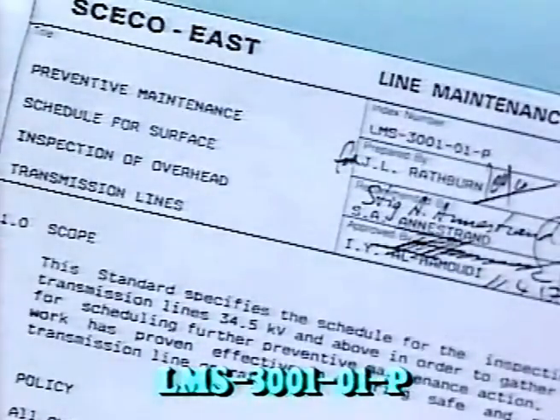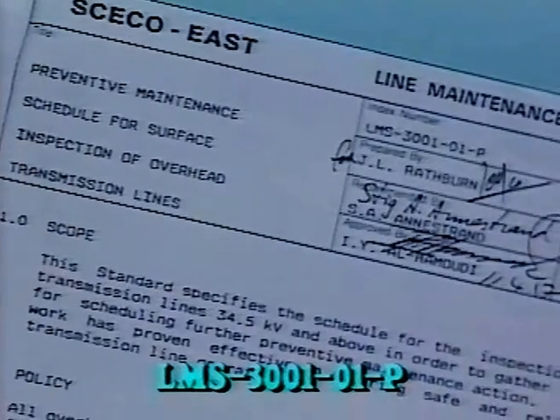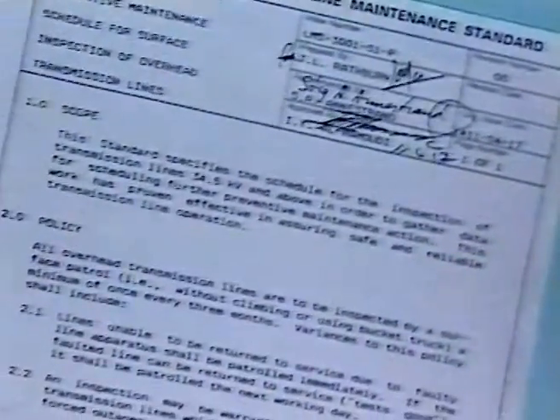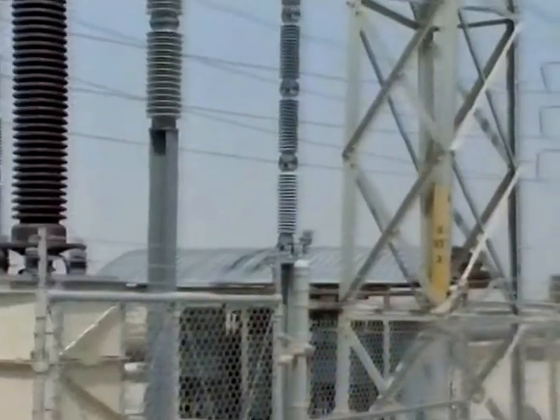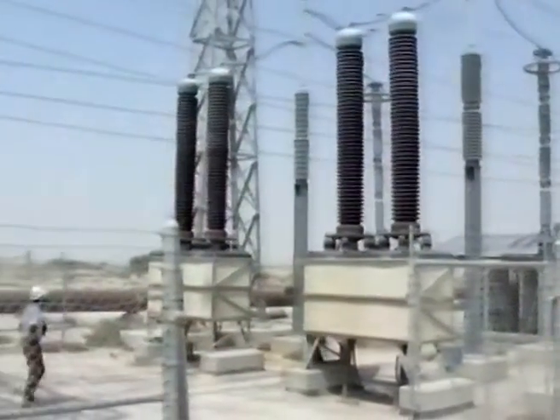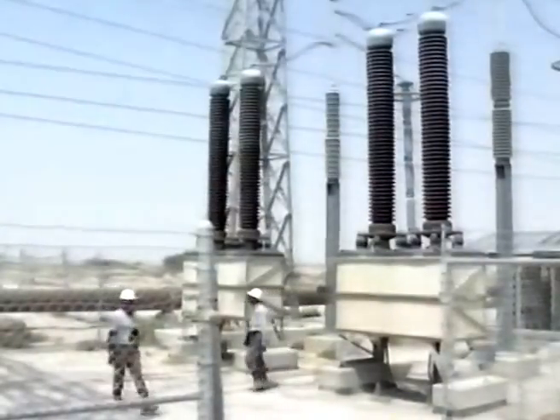LMS-3001-01-P specifies the schedules that will be used to carry out these inspections. Transmission lines 34.5 kV and above must be inspected in order to gather data for scheduling further preventive maintenance action. This work has proven effective in assuring safe and reliable transmission line operation. We will show you the procedures involved on how to effectively perform the surface inspection of overhead transmission lines, or ground patrolling.